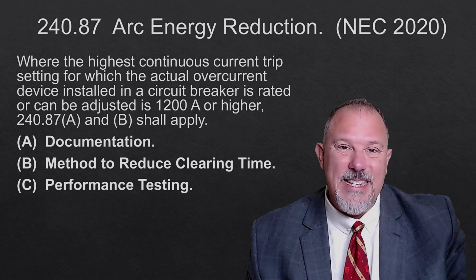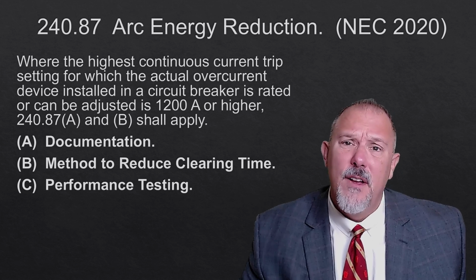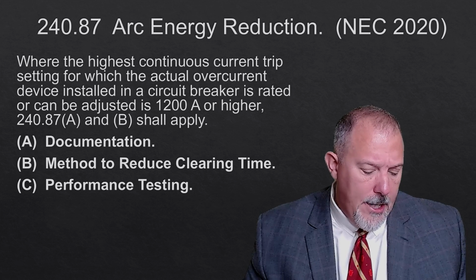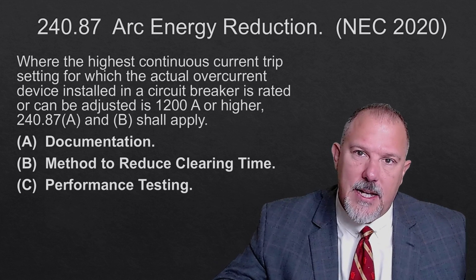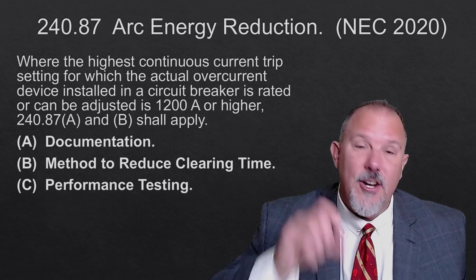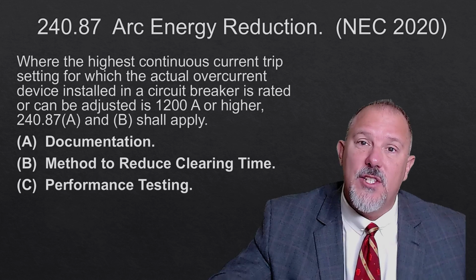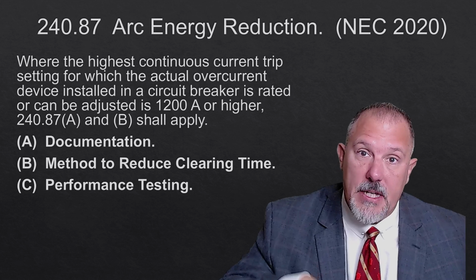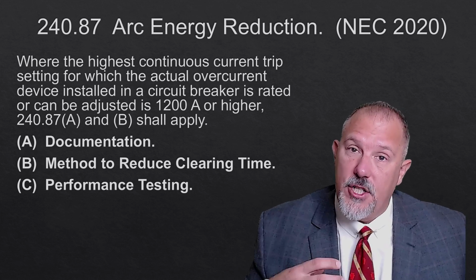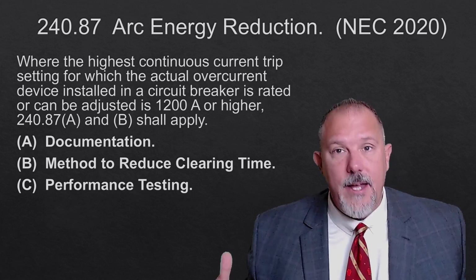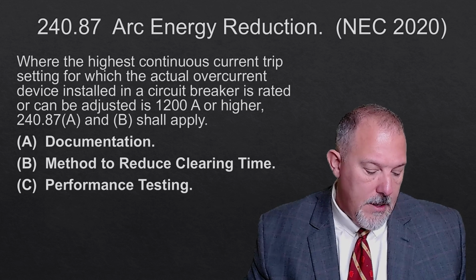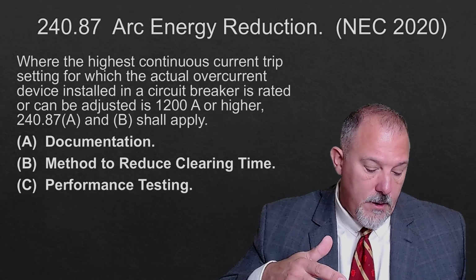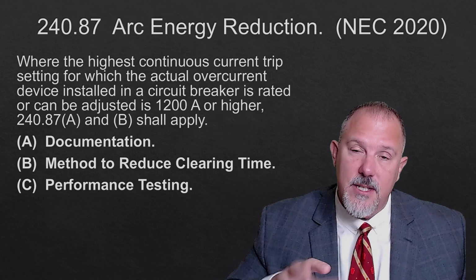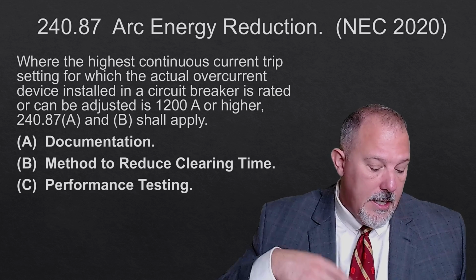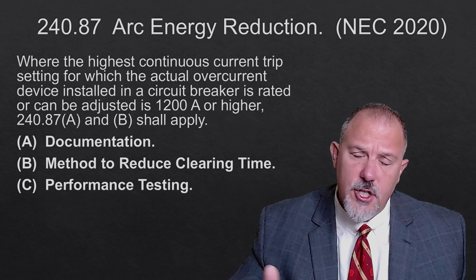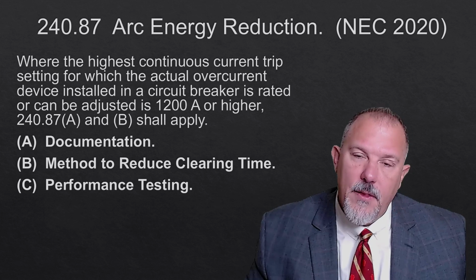So zone selective interlocking, differential relaying, that's been around for ages. Energy reduction maintenance switch with local status indicator. An energy reducing active arc flash mitigation system. I would say this is one of the most relatively new applications or examples of technology that reduce equipment damage and help the electrical worker. You have the instantaneous trip, not being permitted to be adjusted in the field, but the instantaneous trip could be leveraged for arc flash reduction, and so could the instantaneous override. And then you have the approved equivalent means.